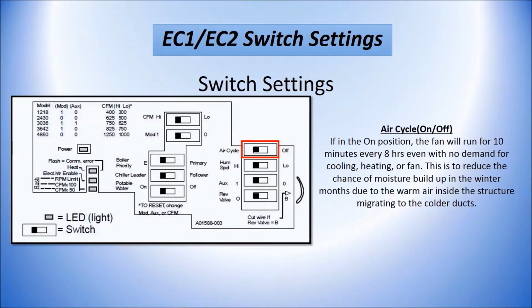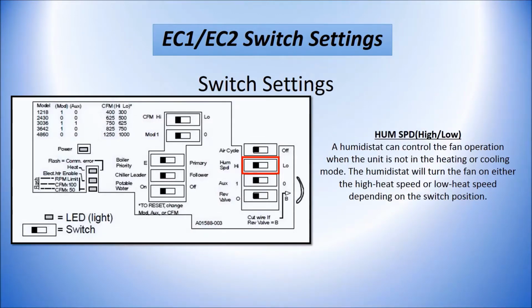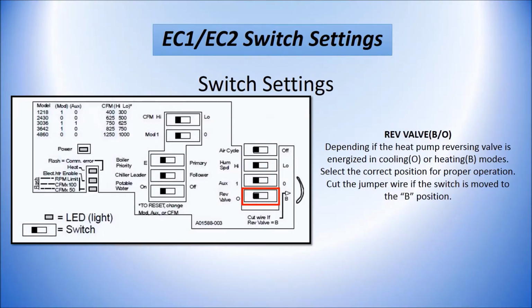If the air cycle switch is in the on position, the fan is going to run for about 10 minutes every 8 hours. This is going to reduce the possibility of the warm air inside the structure migrating to the cold ductwork and causing moisture problems. If you're using a humidistat to control the fan on the EC board for humidity, you have two selections, either a high heat speed or a low heat speed, depending on the switch position. The reversing valve switch has two positions, either O or B, depending on the model of heat pump that you have. If the reversing valve is energized in cooling, you're going to have it in the O position. If it's in heating mode, you're going to have it in B position.